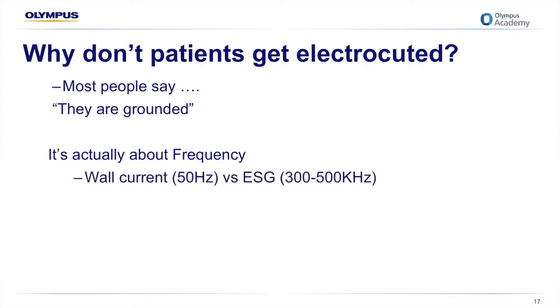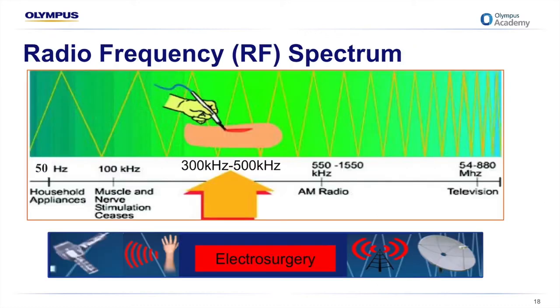If you recall earlier, I mentioned that out of the wall we receive current at 50 hertz, and the generator ramps it up to about 300,000 times per second, or 300,000 hertz. Well, if you look on the next slide, muscle and nerve stimulation ceases. So it's actually counterintuitive, but our nerves and muscles are unable to detect this frequency at such a high rate. Electrosurgical generators are often referred to as high frequency or radio frequency generators, and that's simply because they operate in that high frequency range.